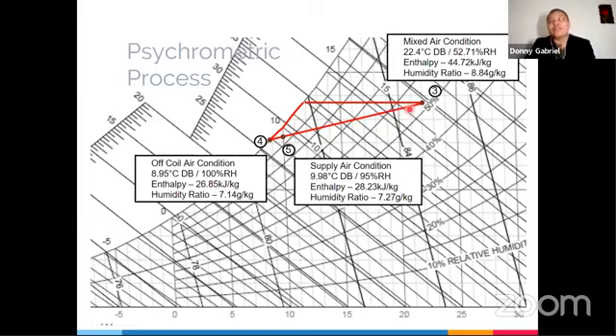But the bypass factor is not actually 5%. So you need to check your coil manufacturer. The usual bypass factor is about 10% or less. So it cannot exceed 10%. Some of the bypass factors that I've seen, the good ones, they have at 5%, 4%. So you need to check your manufacturer.